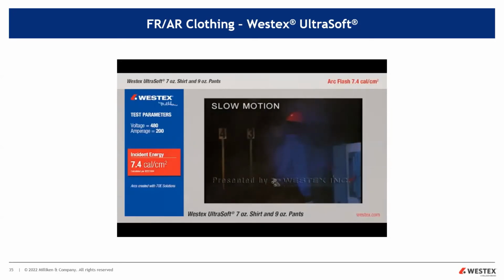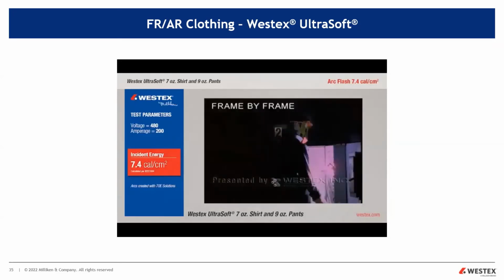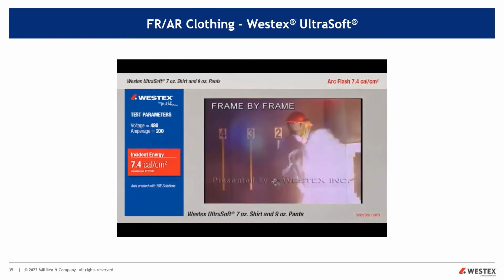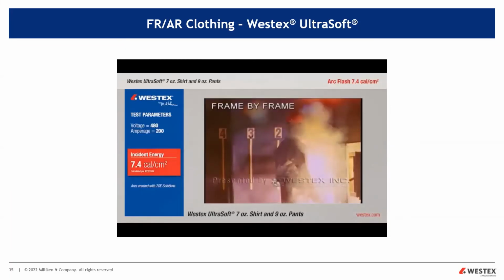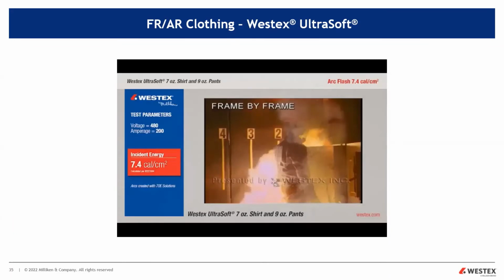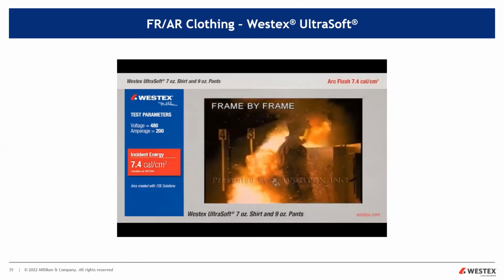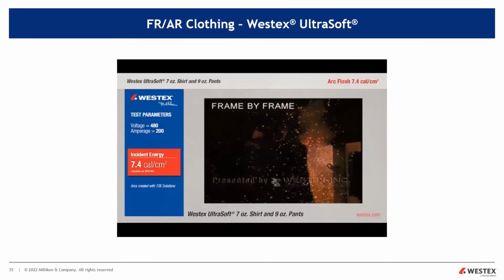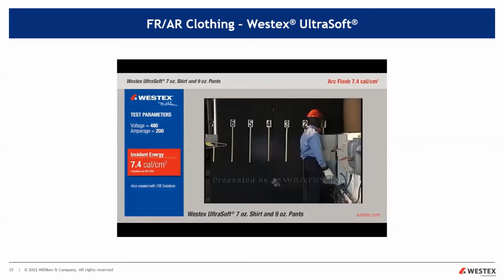Frame by frame will give us another look at the arc. See it come out of the box, up the face and chest of the mannequin, and around to the left as well, and around the back. Arcs do unpredictable things. This one was at least 4 feet out of the arc gap. Okay, so there's risk with both types of programs. I mean, the flame-resistant arc-rated shirt could be sitting in the truck, or it could be sitting on the work cart. You've got to wear the stuff.